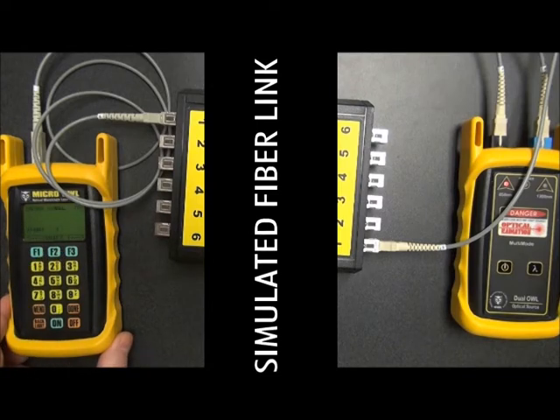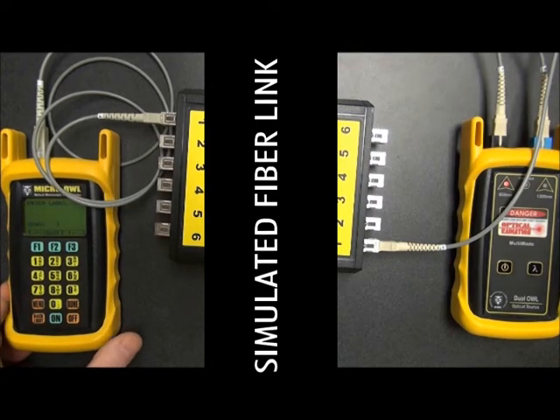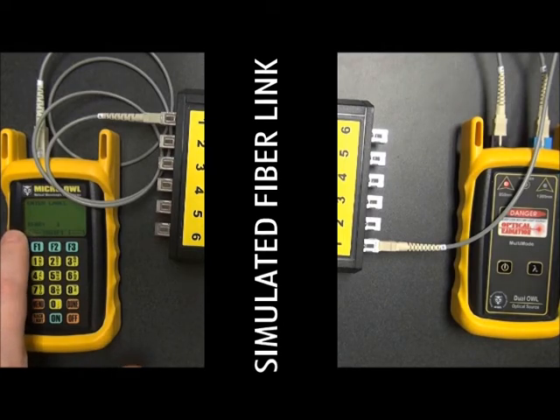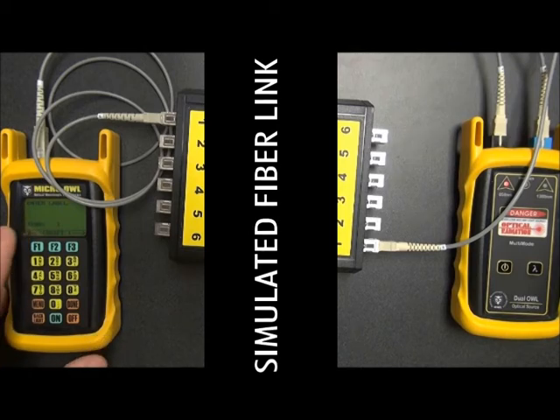And for the first reading that you store for this particular link, it's going to ask you to change this fiber label. Now this fiber label is simply a prefix for the port number that you're testing at that point. The micro-owl will automatically append a fiber number at the end of this prefix. So this could be used to further name the fiber link that you're testing. For our purpose today, I'm just going to leave it as the default value here.